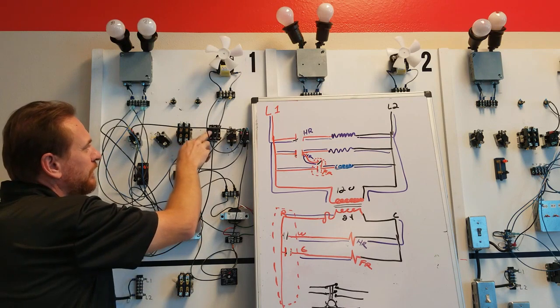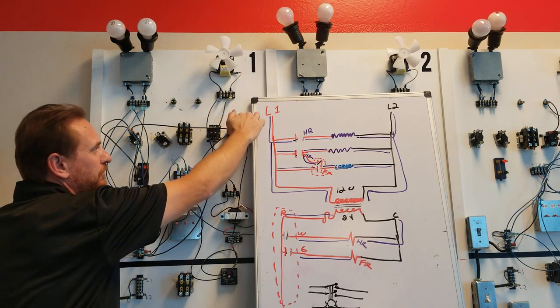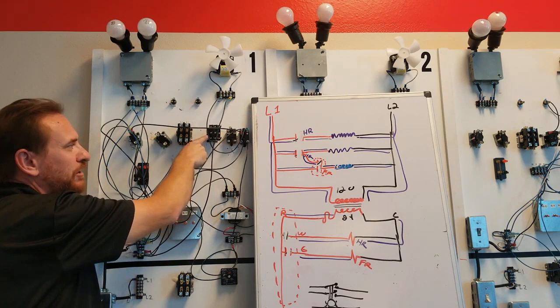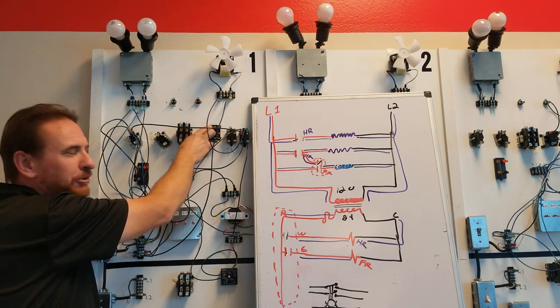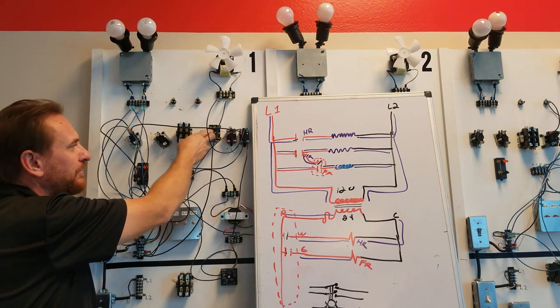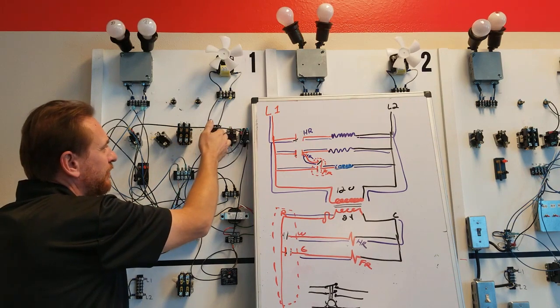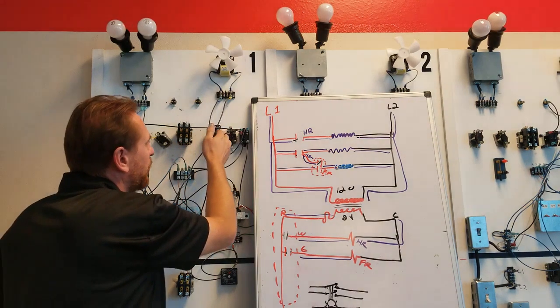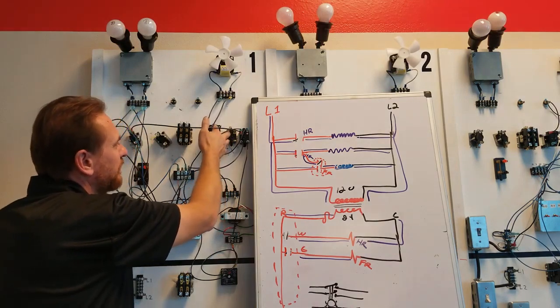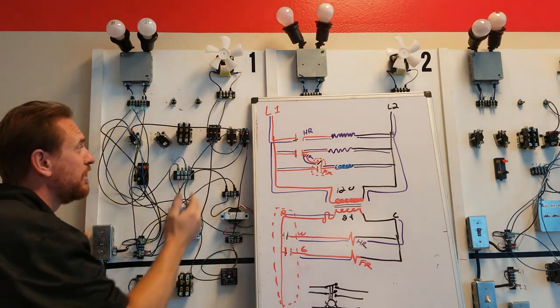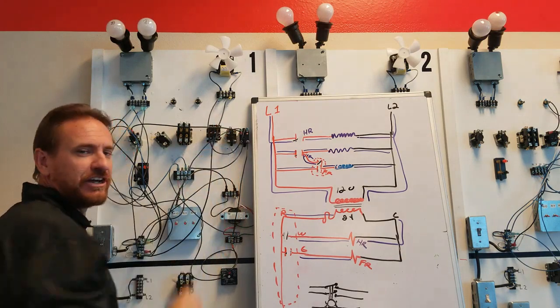It has numbers 1, 2, and 3, just like we have 1, 2, and 3 terminals here. But it has a little drawing on here. Between 1 and 3 is normally open. Between 1 and 2 is normally closed. Then we have another set, 5 and 6. Between 4 and 5 is normally closed. Between 4 and 6 is normally open. So it tells you. Then we have another set over here that's not numbered at all.